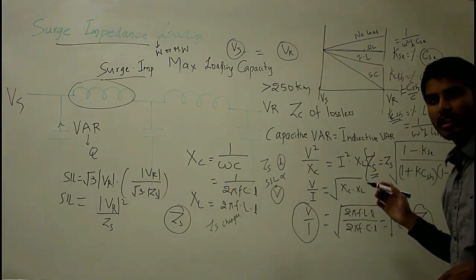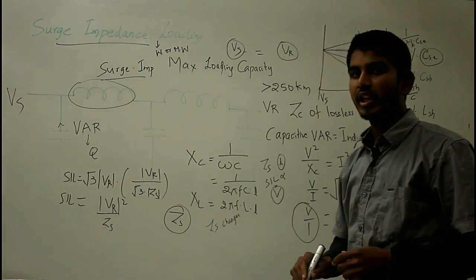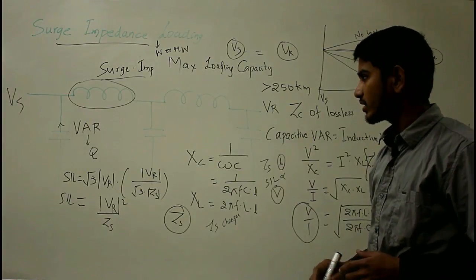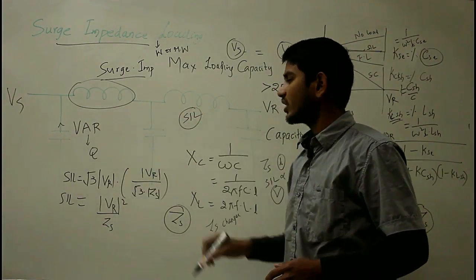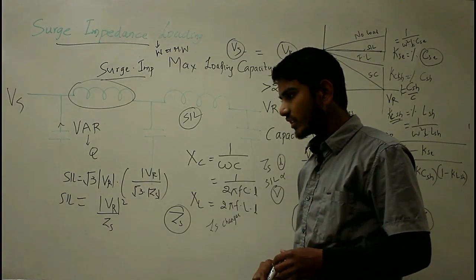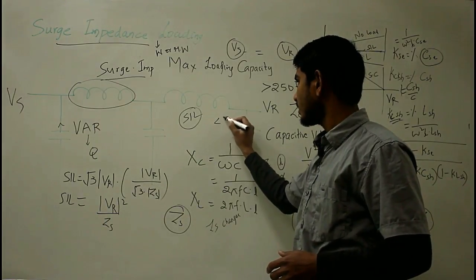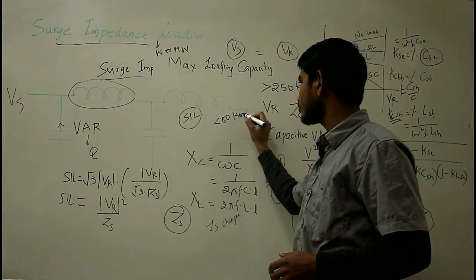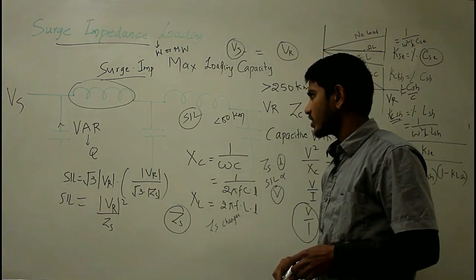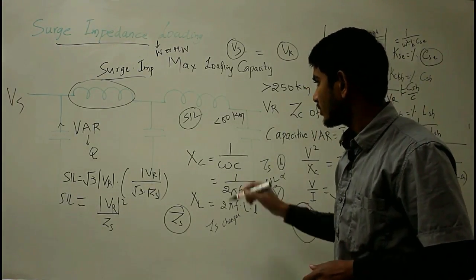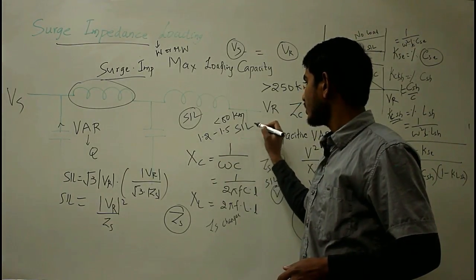Turning to the applications of surge impedance loading: power engineers normally represent line loading in terms of SIL. The maximum load that a short transmission line (less than 80 km) can transfer is about 1.2 to 1.5 times the SIL without any compensation.